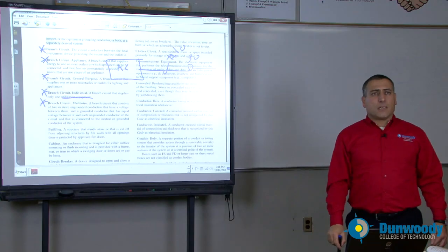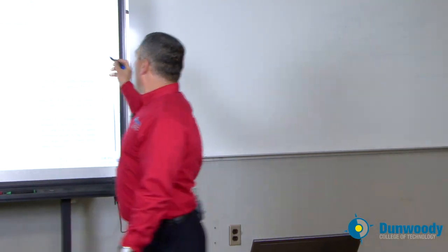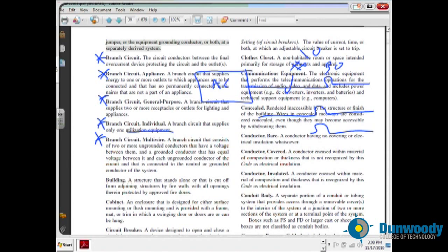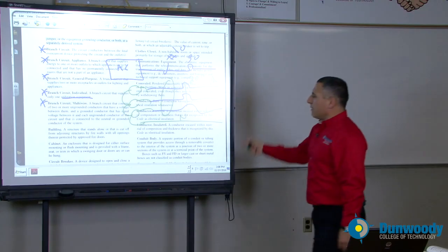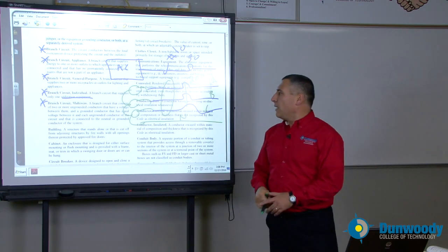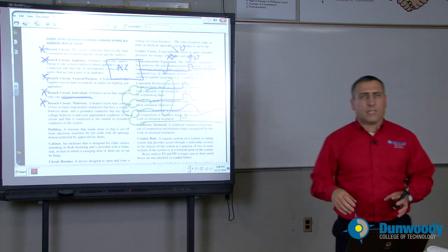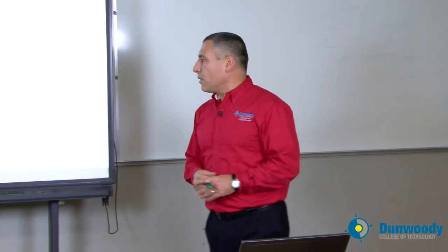Branch circuit multi-wire: if I have a multi-wire branch circuit, say I have two rows of lights over here. Here's a multi-wire branch circuit — three hot conductors with a neutral. I have multiple lights fed from three-phase power: phase A, phase B, phase C, with three hot conductors tied together at 20 amps and a neutral. That's what we call a branch circuit multi-wire. So two hots or more with a neutral — very important to understand that concept.